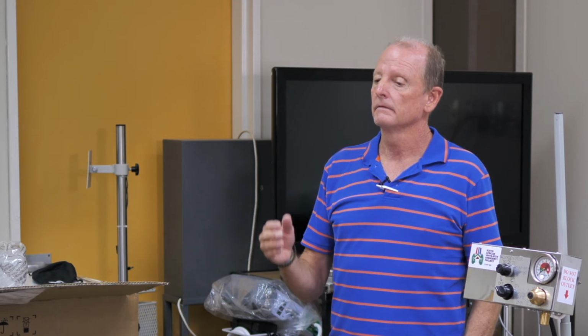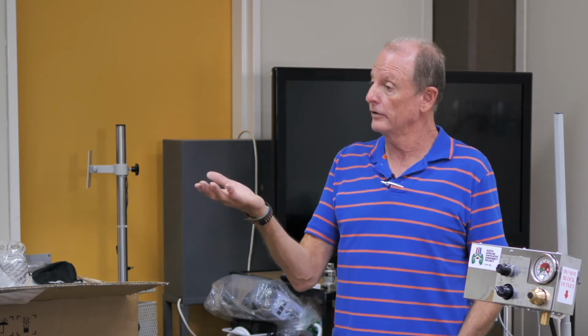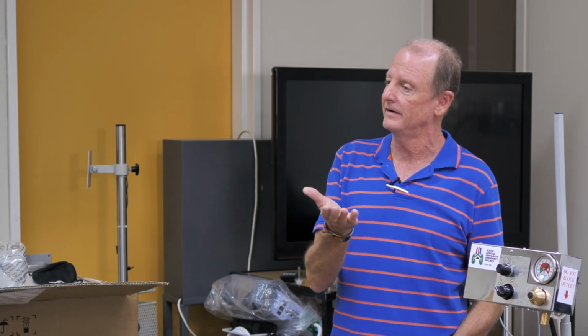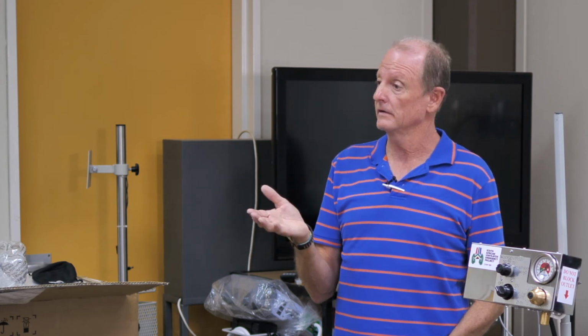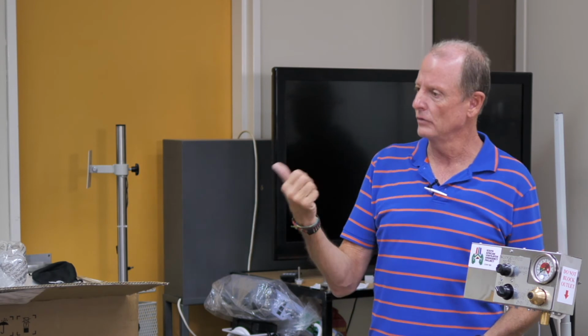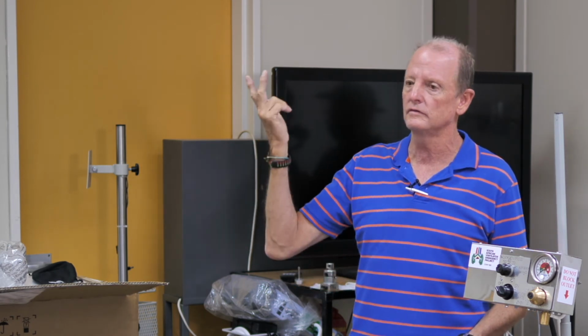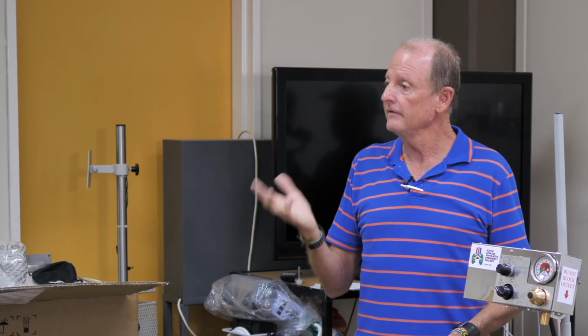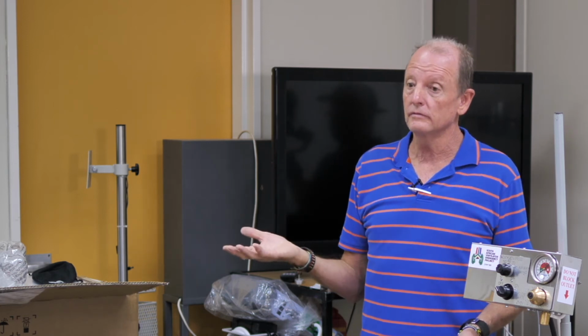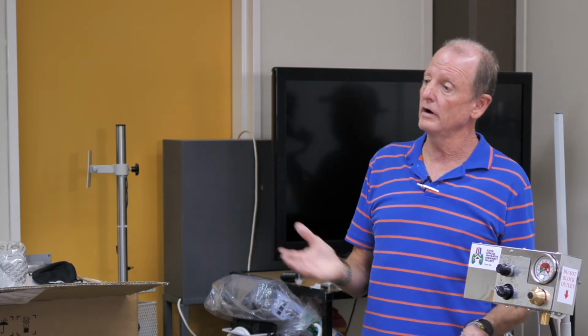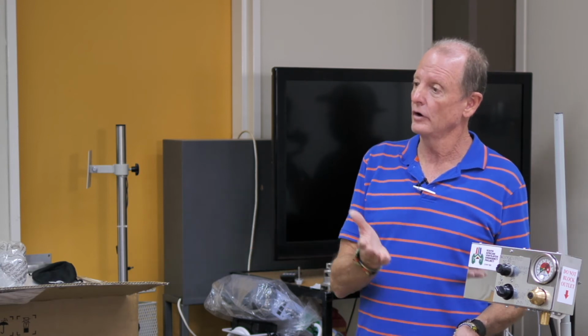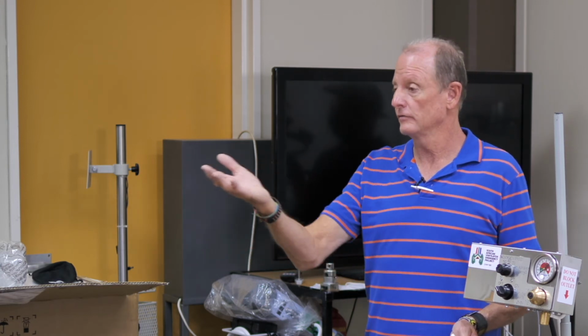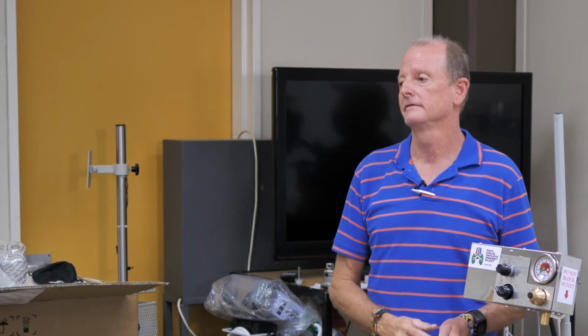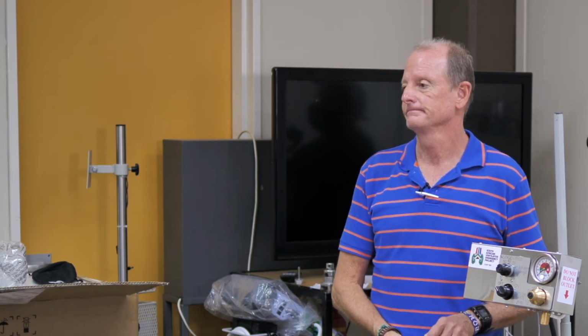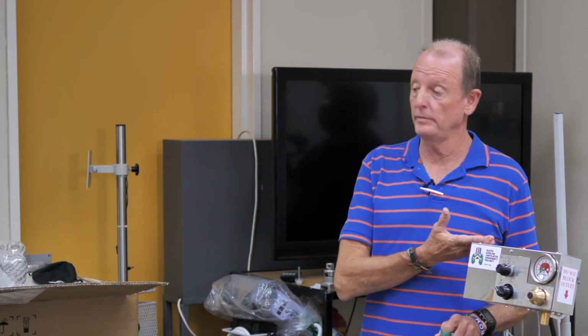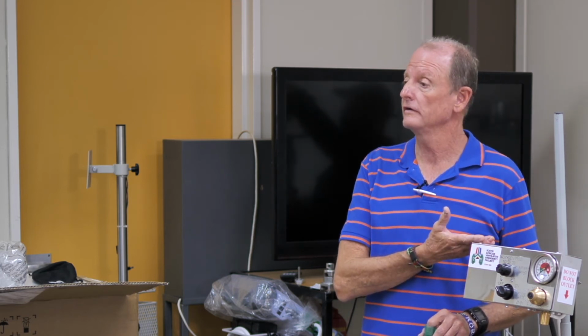But a lot of wards have got oxygen, but they don't have air. A lot of wards are like that. I mean, you go into a ward, they're not going to have air. Your ICUs, your high cares, your NICUs, they've all got the air. And those are normally always full up anyway. So basically your COVID ward should have air and oxygen. Unless you've got a Venturi system, which then you don't need. So these can be run off cylinders. Oxygen air cylinder.